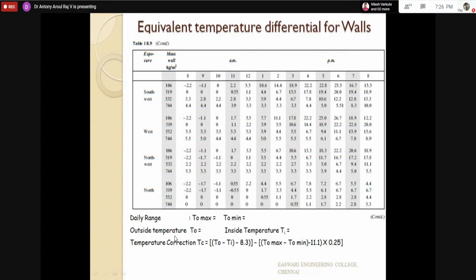This is the daily range, considering both outside and inside temperatures. Inside is the conditioned temperature, outside is the ambient temperature. Based on these, we apply a correction along with the daily range correction, putting both together for your specific place. For example, in Chennai, the daily range is higher, the outside temperature is higher, and the inside temperature is lower, so the overall temperature correction will be higher. But beyond 30° north latitude, the daily range may not be as high, and the outside temperature will not be as high as in Chennai, so the correction there will be smaller.